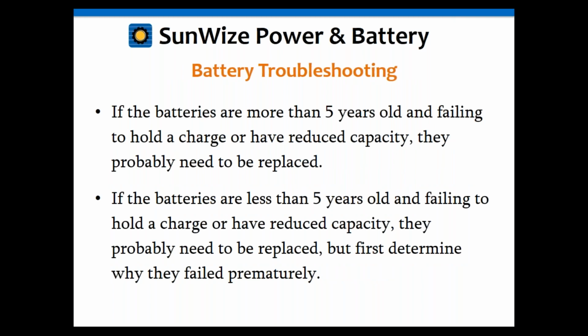Batteries. I know I talked earlier about how you can find out if they've gone bad or not, with the trending and everything else, but some of the other things to look for is if they're old or not. If you've got batteries that are more than 5 years old, that's when you need to start looking at them to determine if they need to be replaced or not. Most good solar batteries in a properly designed system that's been maintained correctly should last about 5 to 8 years. I mean, it's very common to get 8 years out of them.